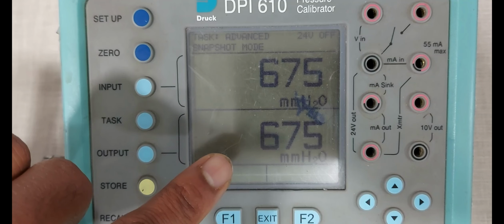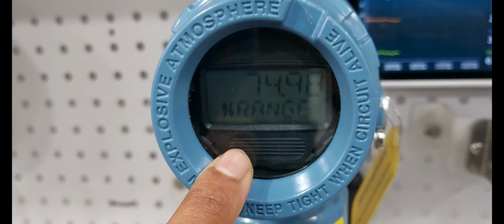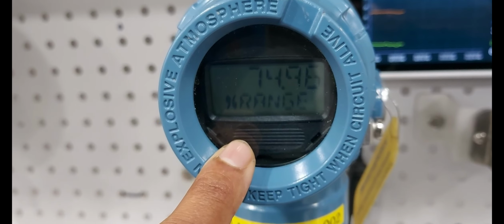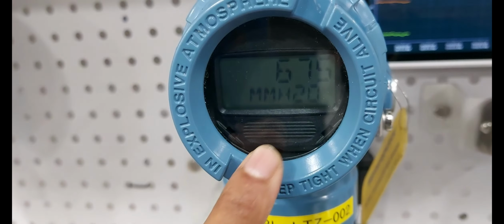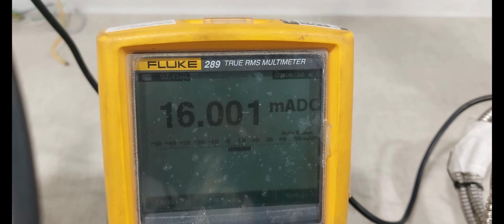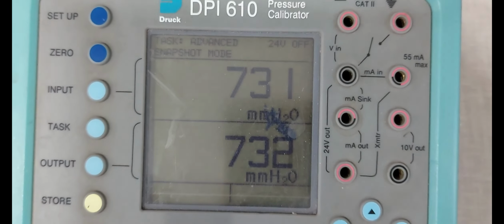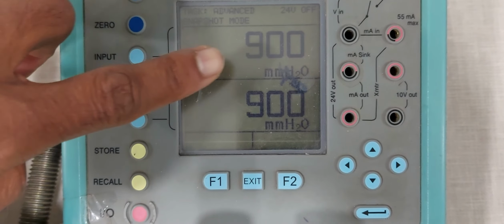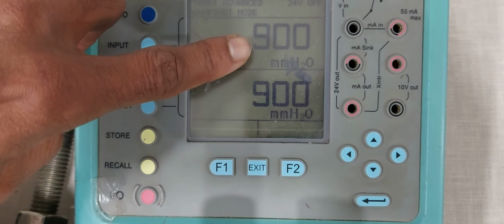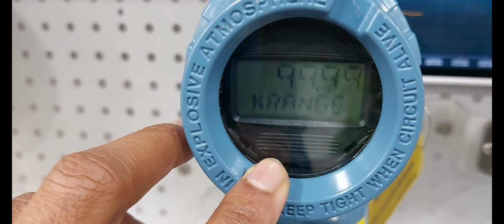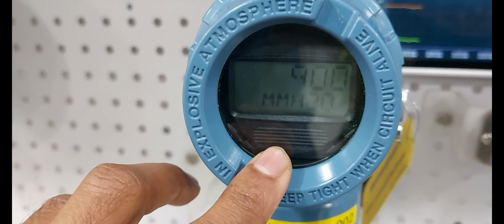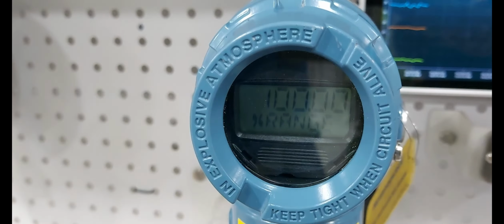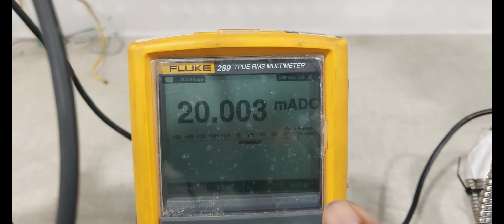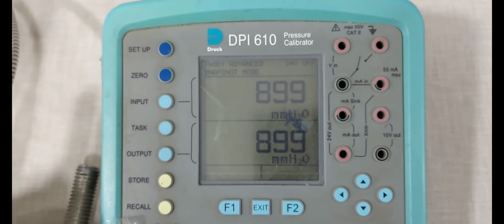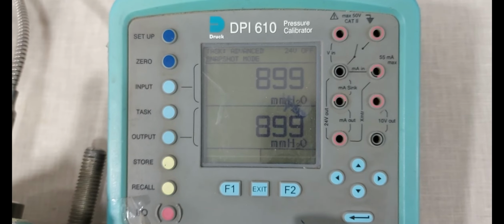675 mmH2O reached, 75%. Now transmitter display showing 675 mmH2O. Percentage showing 74.96. Now transmitter output is showing 16.00 milliamps. Next we are moving into the 100% value. Now full span range is reached, 900 mmH2O. Transmitter display showing 99.99%, 900 mmH2O. Now transmitter is at full range, 20.003 milliamps.